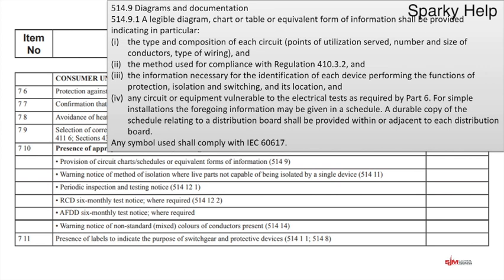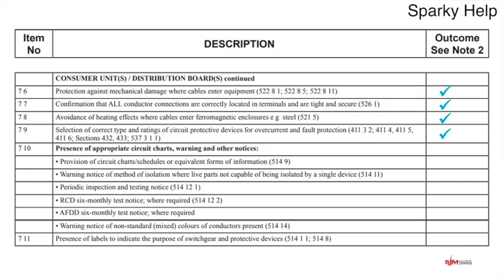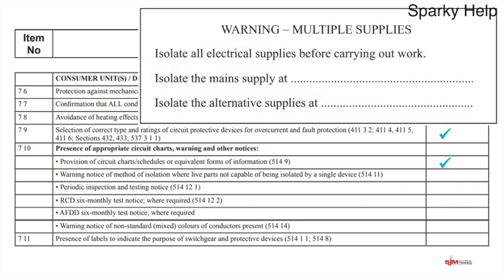So each distribution board we ever go to, we should see this. Obviously that always happens. So if we haven't got that, then we'd be looking for it. If we have got it, it becomes a tick. Warning notice of method of isolation where live parts are not capable of being isolated by a single device. So if you've got somewhere that you can't meet that requirement, then at least you've got warning notices. So have we got them?